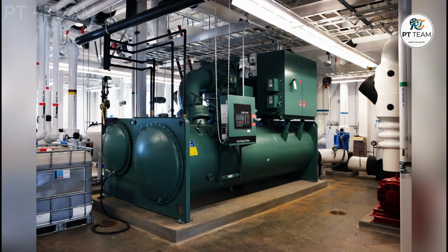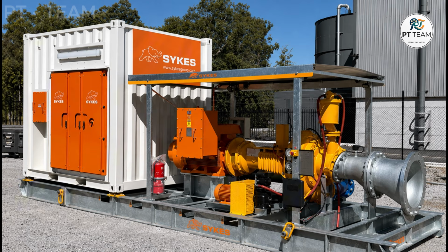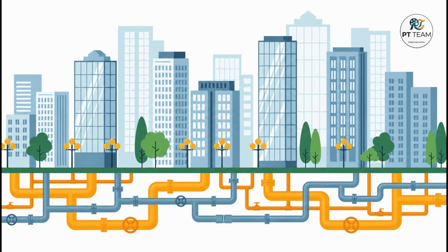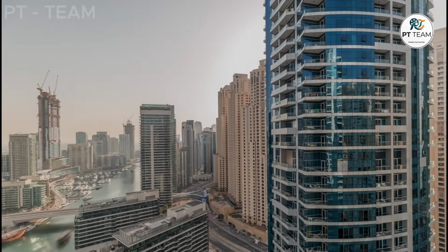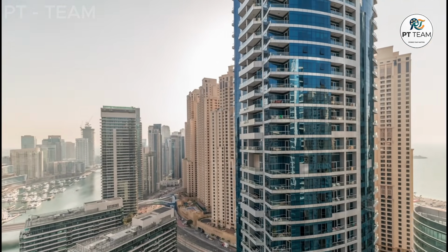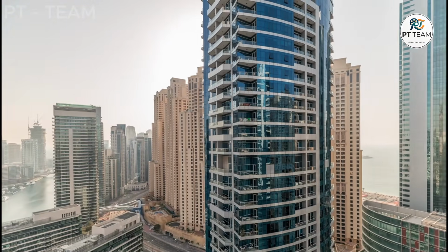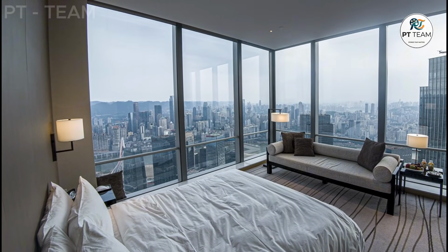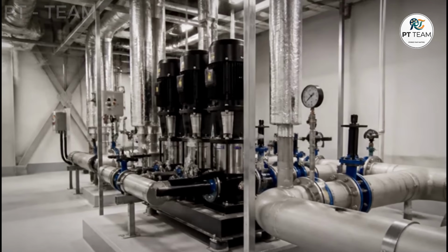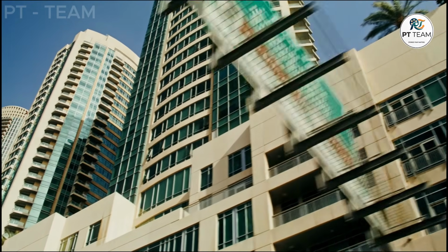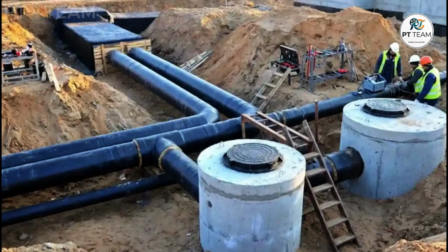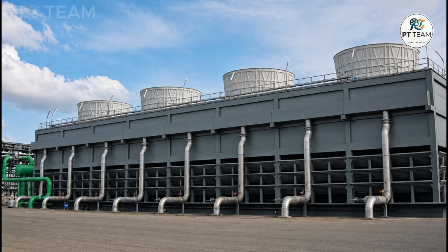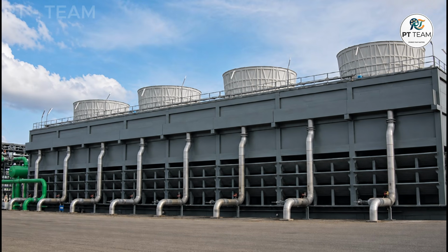The central plant operates industrial chillers to produce chilled water, and powerful electric pumps push that water through the closed underground distribution network toward connected buildings. Inside the mechanical floor of each building, a localized heat exchanger transfers the collected thermal energy from the indoor air directly into that chilled water. That water, now carrying the accumulated heat of the building, flows back through a parallel return pipe to the central plant to be processed and cooled again.